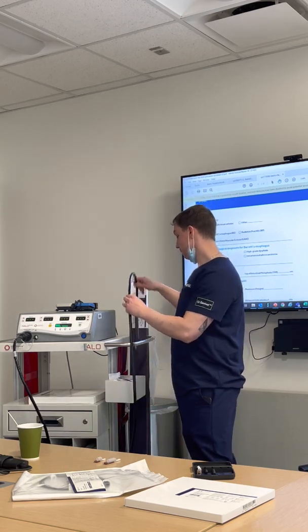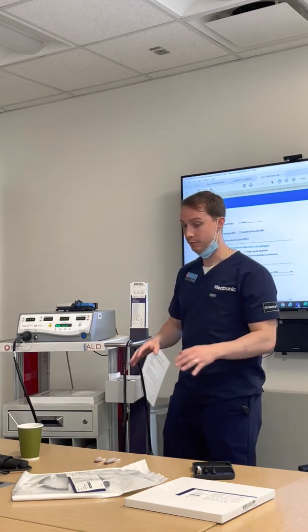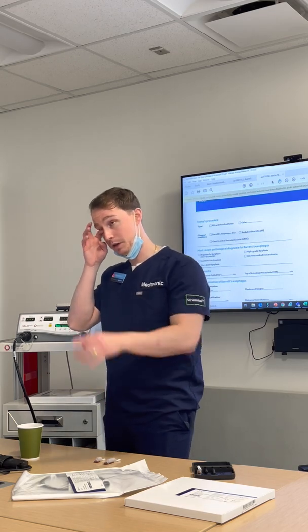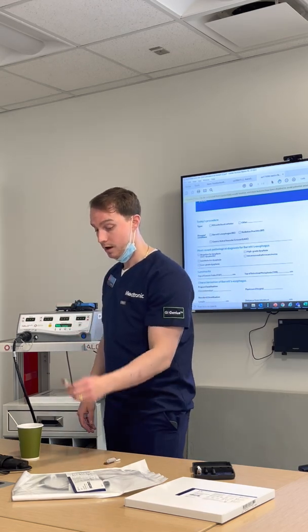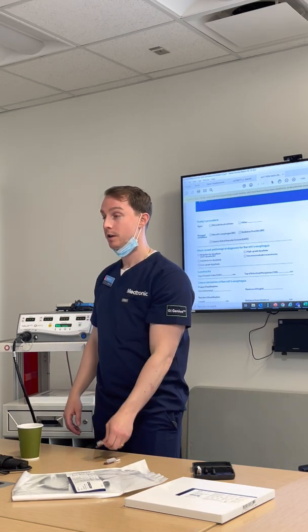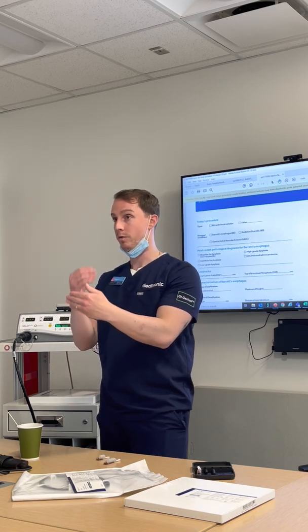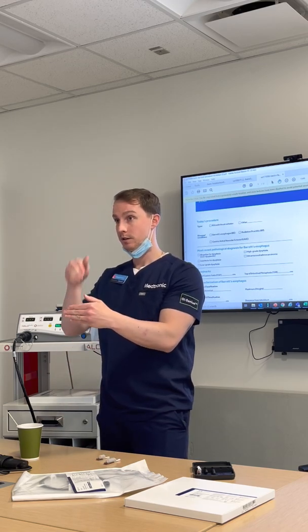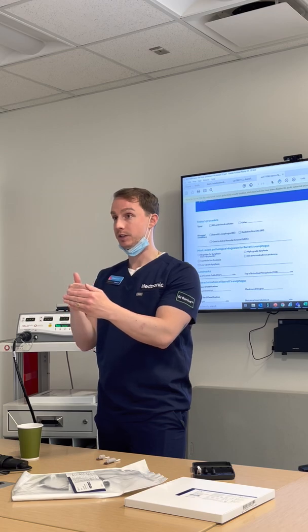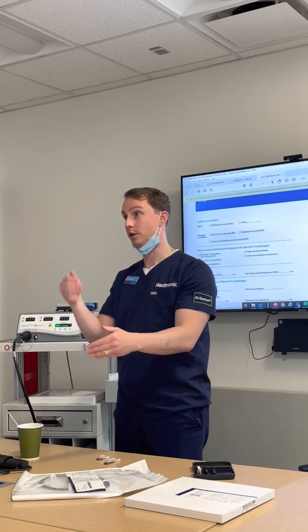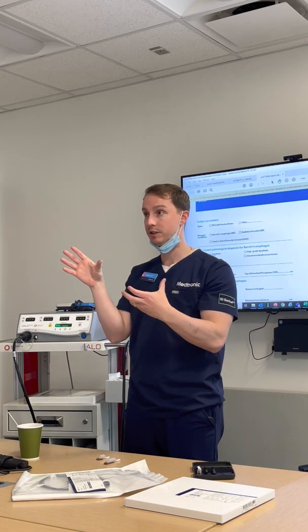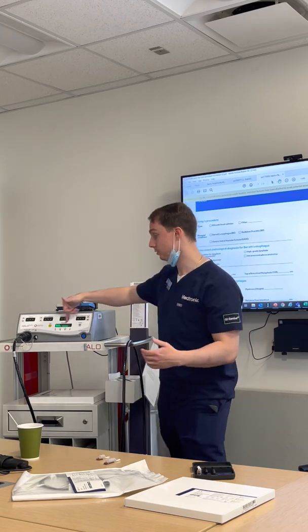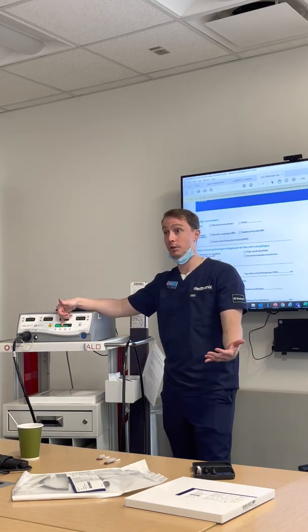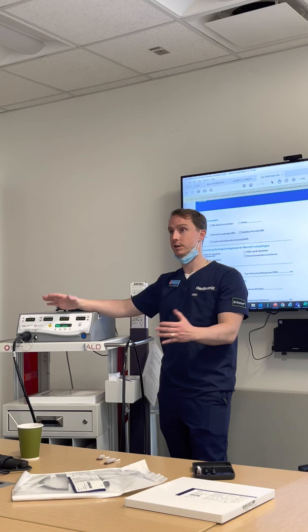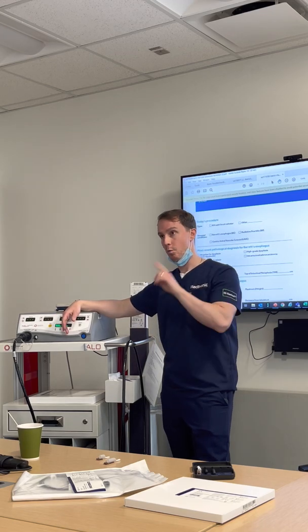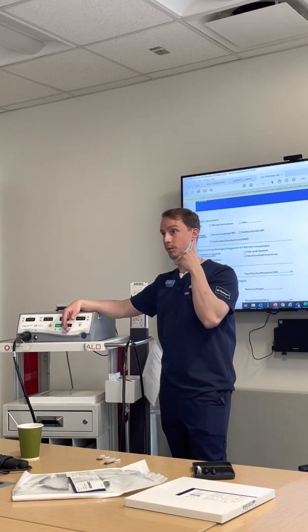For our focal catheters, we have some different protocols. So with through the scope and the 90 catheter, you're going to ablate that same area twice. Then they're going to clean it, ablate that same area twice again, and then pull out. Depending on how many areas they need to treat, that will change the number of total ablations.